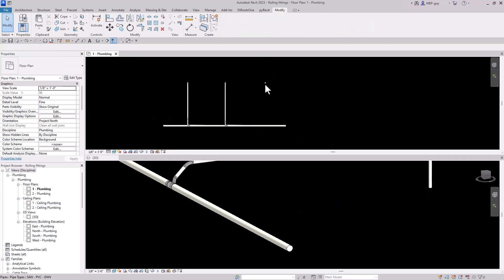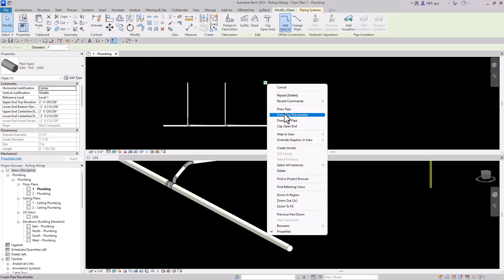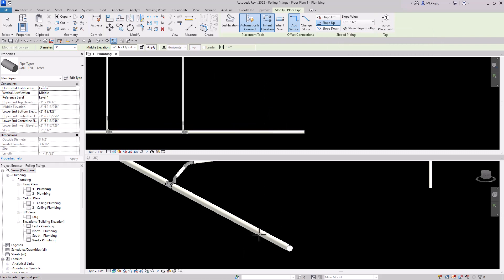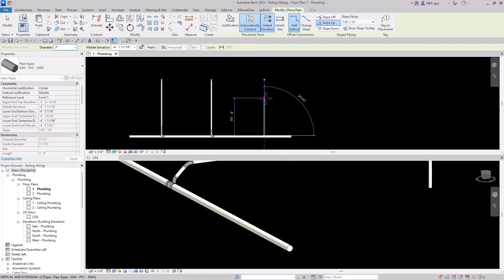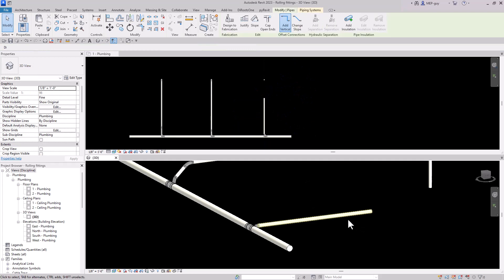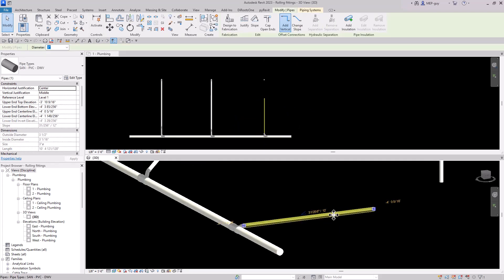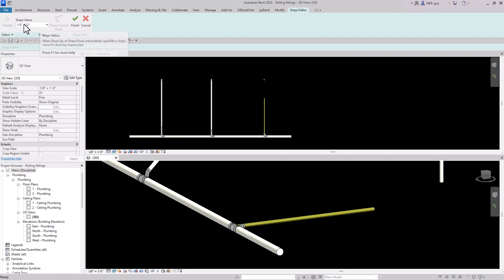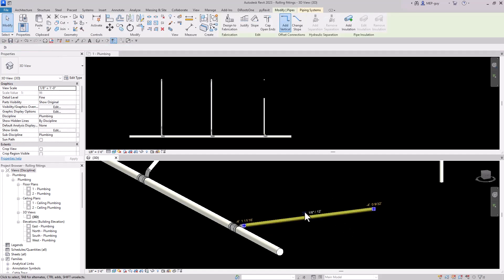Select the pipe, right click, and choose Create Similar. Use Inherit Elevation, set Slope Up, and this time I want to use an eighth of an inch because I don't even need to roll the piping — just go straight from this piece up since it's already at a similar elevation. Draw from the main, click, and start drawing. You can also just go up to Slope, select eighth of an inch, and hit Finish. Now if I select it, everything's perfect.